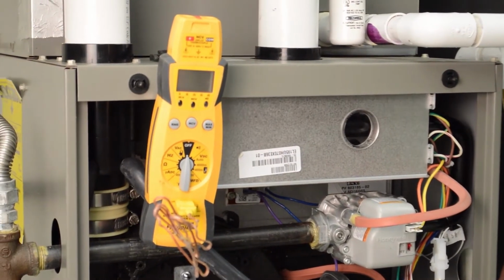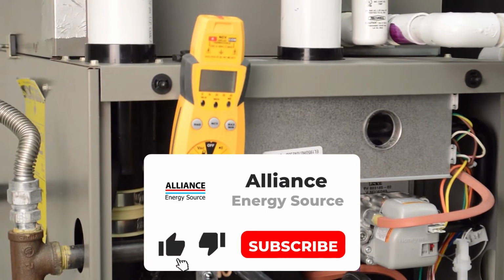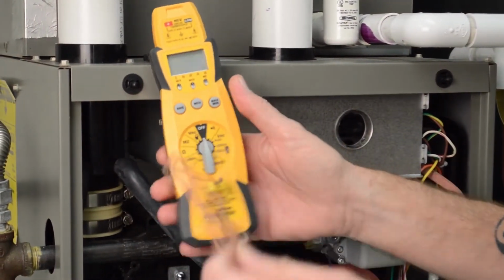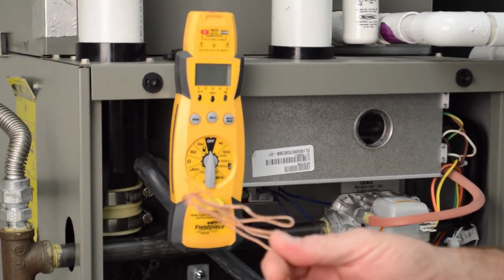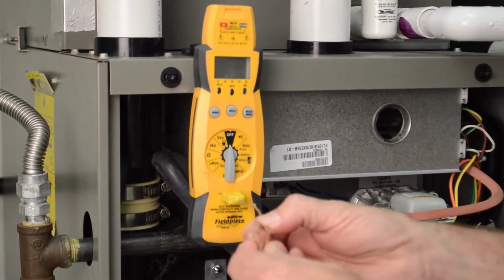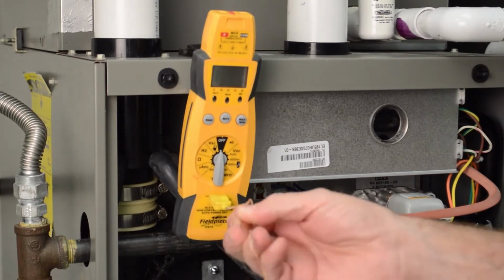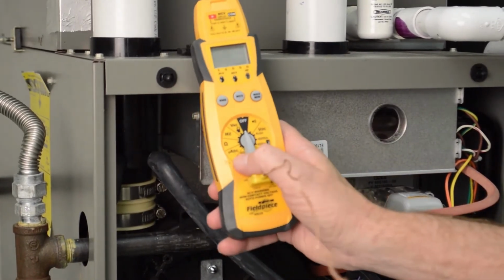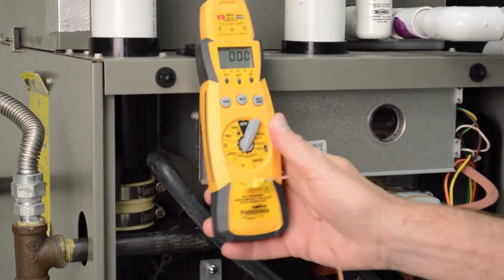Okay, today we're going to be talking about measuring the temperature rise across the furnace. It's a pretty straightforward process, very easy to do. We're going to need one thermometer with either a multiple, a dual head, or a single head. Make sure you turn the thermometer to a reasonable calibration point on it.